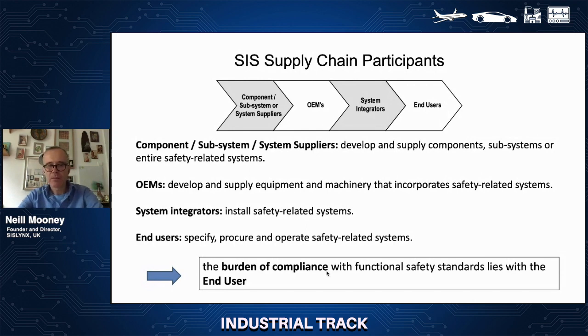Now, this may not be an explicit legal requirement. But for example, in the UK, you will have a statement in the overarching safety legislation that requires the end user, the operator of the plant that incorporates dangerous hazards, to comply with international best practice in the design and operation of their facilities. And that typically means that compliance with functional safety standards is considered to be best practice. So this is a critical point, that the burden of compliance lies with the end user.